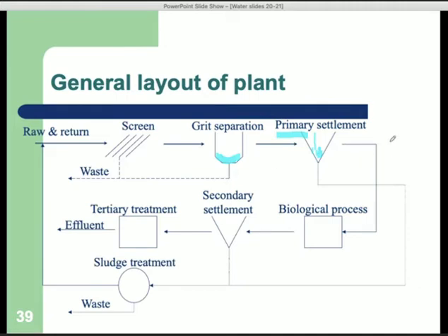What you could do is, if you were really concerned, you could have a second stage here, and this doesn't work so well, does it? But you see what I'm trying to write? So you could have a second stage where you have the DAF. It doesn't tend to happen very much. What is more likely is if you really have a problem with sedimentation, then people would also use coagulants. So again, that's another technology that you take out of drinking water treatment. If the sedimentation by gravity alone isn't good enough, then you would add a coagulant to make sure that the particles clump bigger and settle faster.